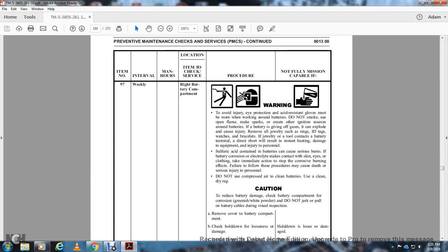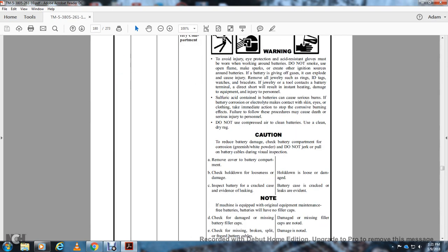The failure to follow these procedures may cause death and serious injury to personnel. Do not use compressed air to clean batteries. Use a clean dry rag to reduce battery damage. Check the battery compartment for corrosion, greenish white powder. Do not jerk or pull on battery cables during the visual inspection.